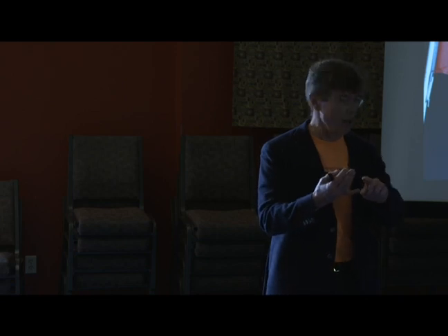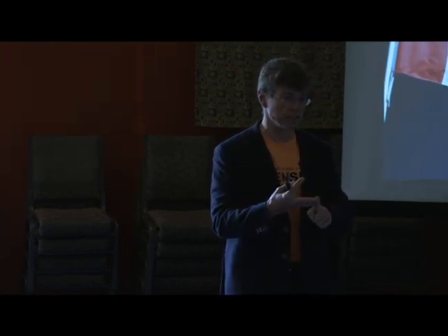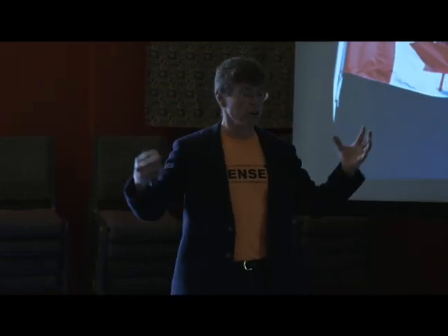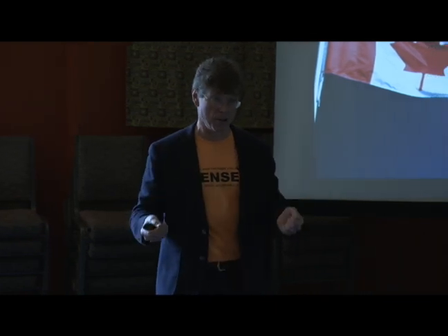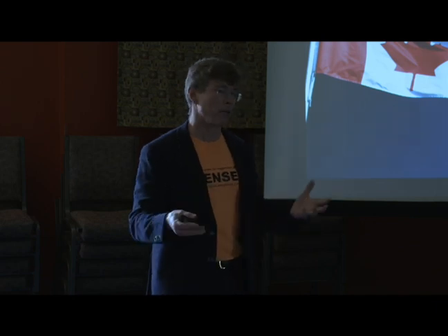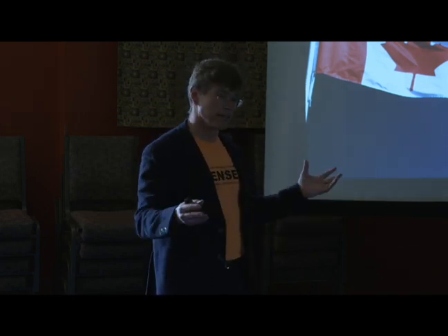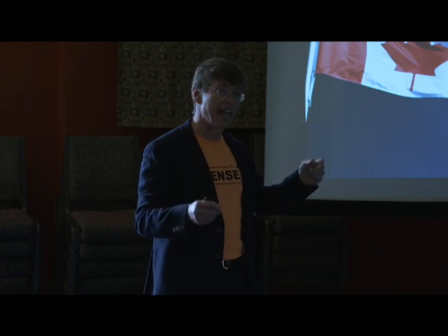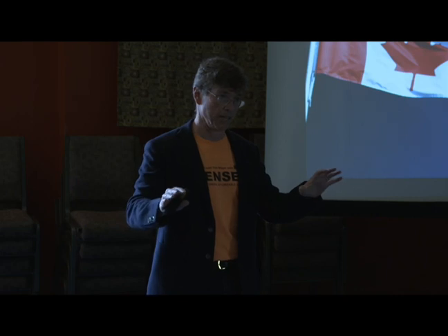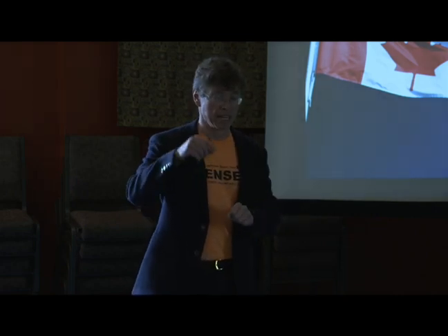And it's a combination of very cold weather, outages of 2 major transformers on the east side, 6 local generation plants turned off for some reason, and this 1,500 megawatts to Canada. You put all those circumstances together, and then you start getting overloads on PSE's equipment. We say, okay, but how long would that problem persist? Well, in 15 minutes, this flow would be gone, and then 80% of the overloads on PSE's equipment would be eliminated. This was found by Bellevue's independent analyst.